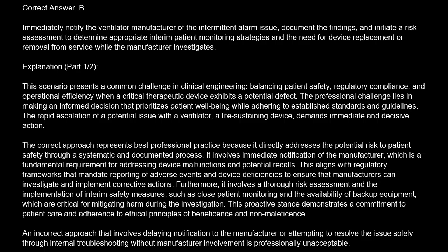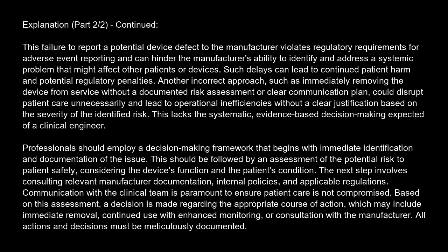An incorrect approach that involves delaying notification to the manufacturer or attempting to resolve the issue solely through internal troubleshooting without manufacturer involvement is professionally unacceptable. This failure to report a potential device defect to the manufacturer violates regulatory requirements for adverse event reporting and can hinder the manufacturer's ability to identify and address a systemic problem that might affect other patients or devices. Such delays can lead to continued patient harm and potential regulatory penalties.